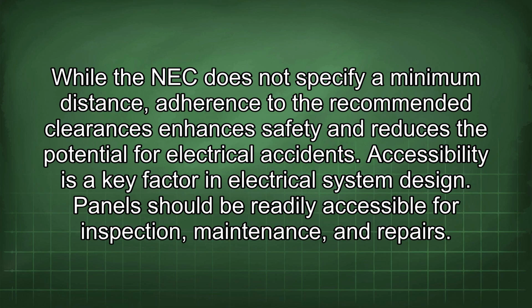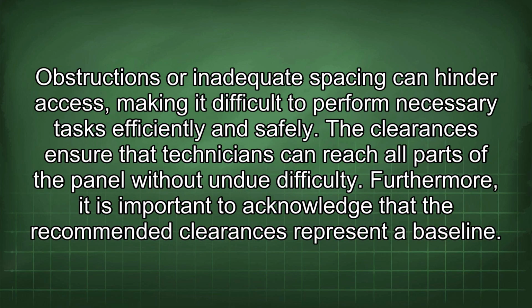Accessibility is a key factor in electrical system design. Panels should be readily accessible for inspection, maintenance, and repairs. Obstructions or inadequate spacing can hinder access, making it difficult to perform necessary tasks efficiently and safely. The clearances ensure that technicians can reach all parts of the panel without undue difficulty.